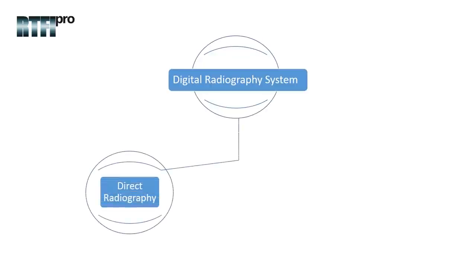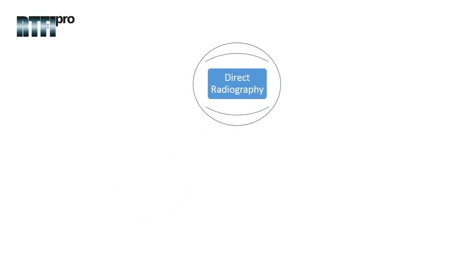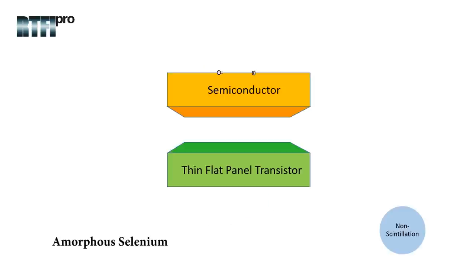Direct radiography, also known as non-scintillation, is composed of amorphous selenium based semiconductor and TFT. This system works by applying a high voltage charge at the top of the surface in nanoseconds just before the x-ray exposure.